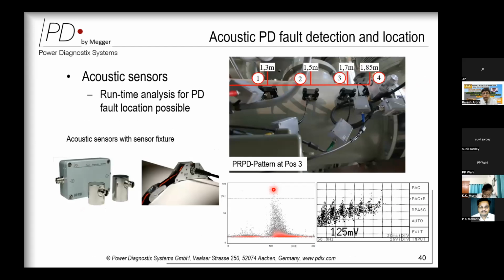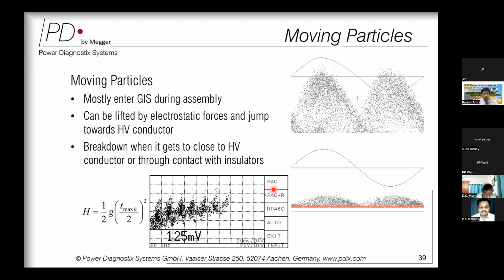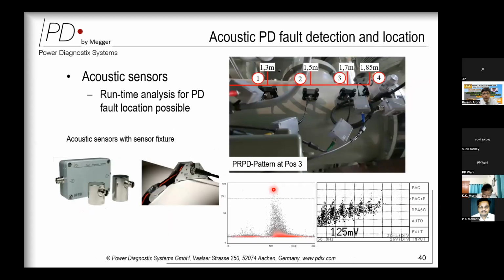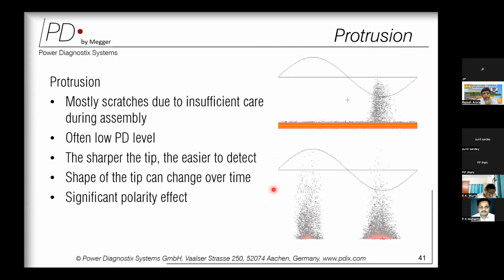So whenever you have a pattern for a moving particle, the next action you need to do is apply an acoustic sensor and measure the bounce height. So probably your measuring instrument should have not only UHF measurement technique, but also support acoustic measurement. In such a defect scenario, you can also measure the height of the bouncing particle.